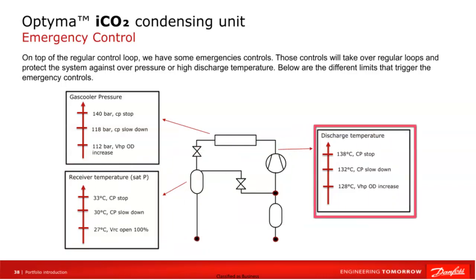Another safeguard ensures that the discharge temperature does not exceed permissible values. A discharge temperature of 128 degrees Celsius forces the high pressure valve to open wider. At 132 degrees, the compressor speed is reduced, and when the temperature exceeds 138 degrees Celsius, the compressor is completely turned off. These additional safeguards guarantee safe and reliable operation of the unit even in hard conditions.